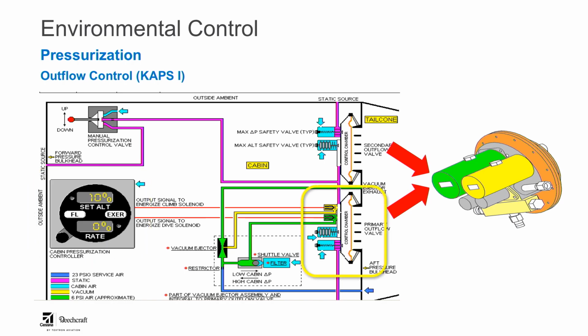We control that using the controller, sending a ground signal to two solenoid valves, a climb and a dive solenoid, located on the primary outflow valve. Those solenoids are always powered, and the controller provides the ground input, a pulsing ground input to either the climb or dive solenoid. We have service air going to a vacuum ejector that can provide either some pressure or some vacuum based on the need, controlled by either the climb or dive solenoid.